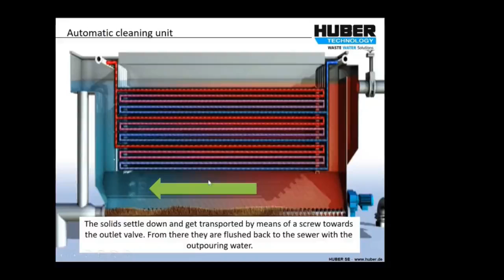So that's just another depiction of the solids flowing, settling out and being carried out via the auger at the bottom. This is highlighting the impact of wastewater on those exchangers. The biofilm is made up of microorganisms which grow on the surface of anything immersed in sewage in no time at all. I can vouch for that, having spent half my life walking around sewage works. You get sedimented solids which are settled out and removed, and the effect is a negative impact on the heat transfer efficiency. So the mechanical cleaning element of our heat exchangers is critical to its success. So too is the stainless steel manufacturing, and there you can see the heat exchanger cleaning efficiency. You can see where the tubular heat exchangers have been cleaned, and then where they haven't been cleaned. It's quite clear, and you can go into one of these things after 5 years and they will still look like that.